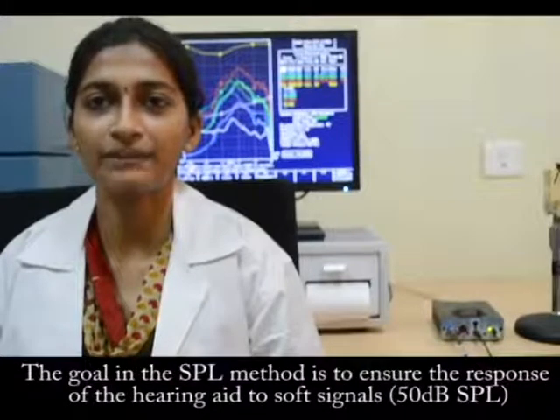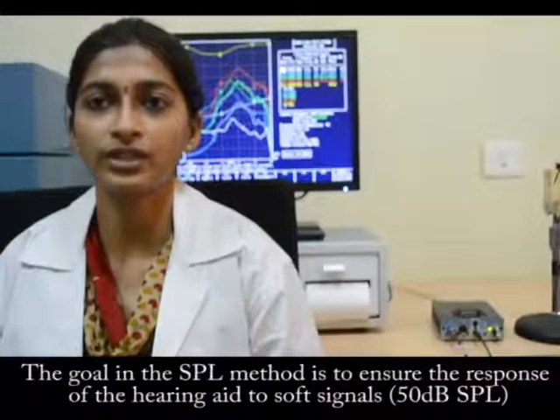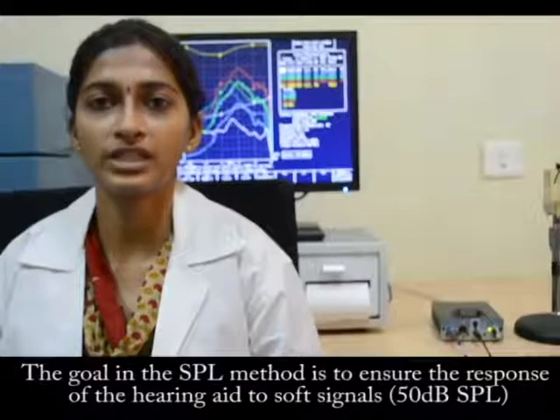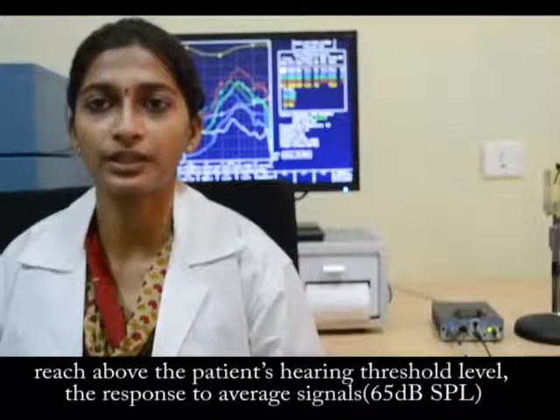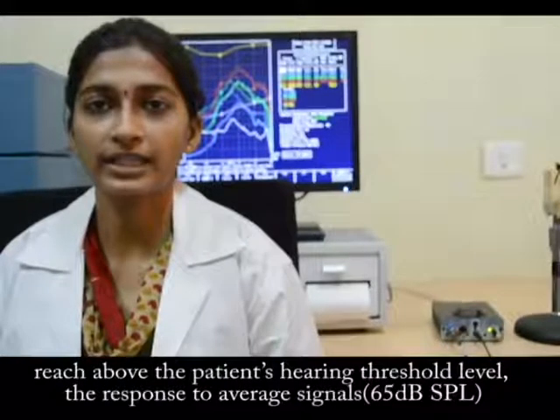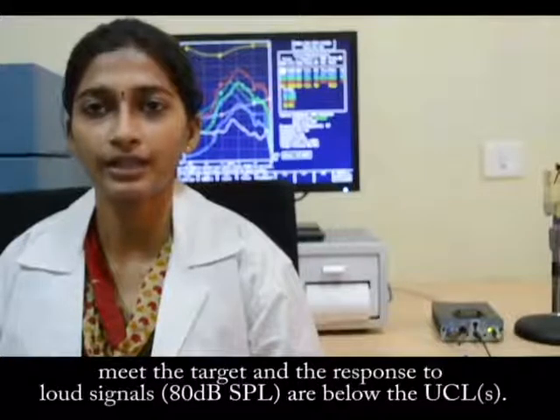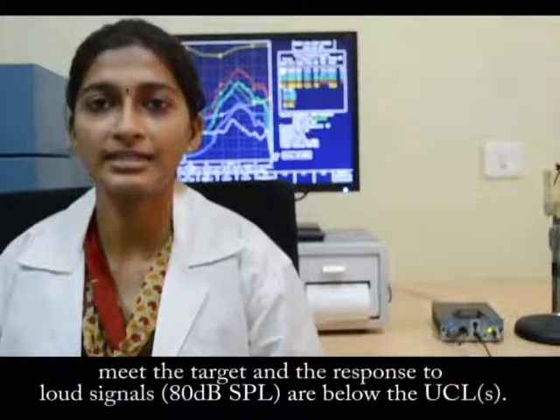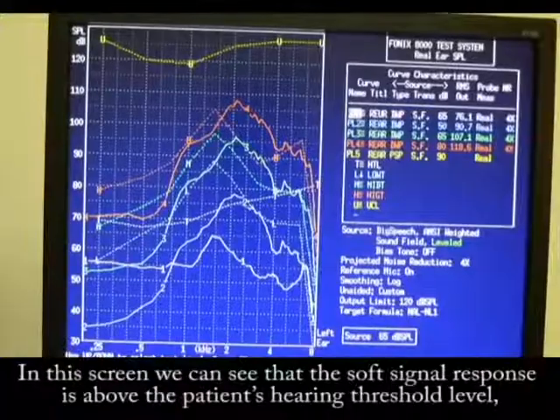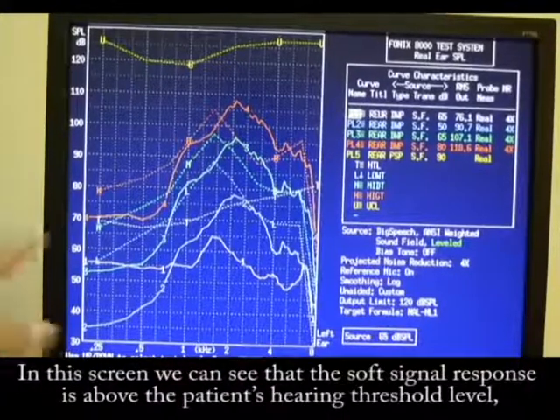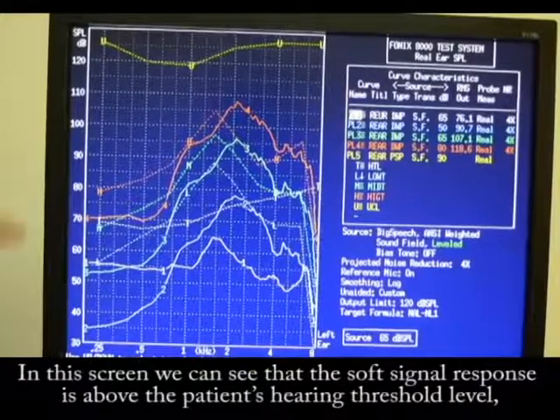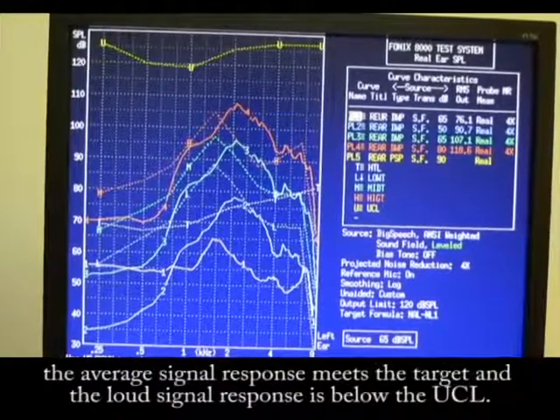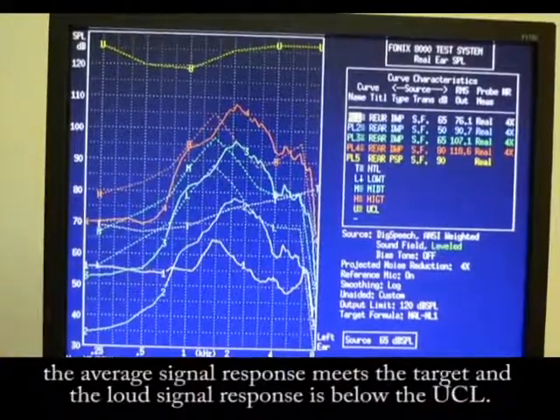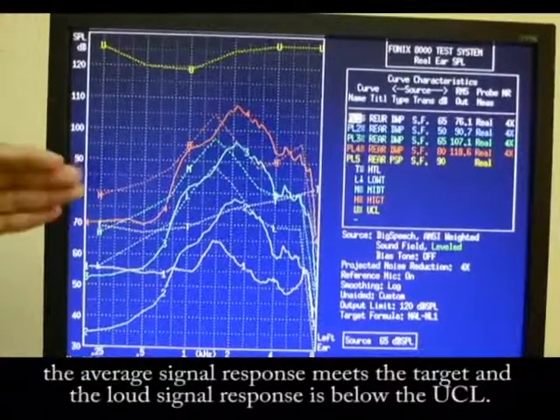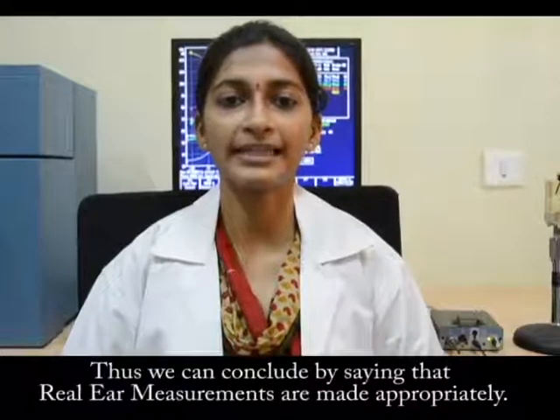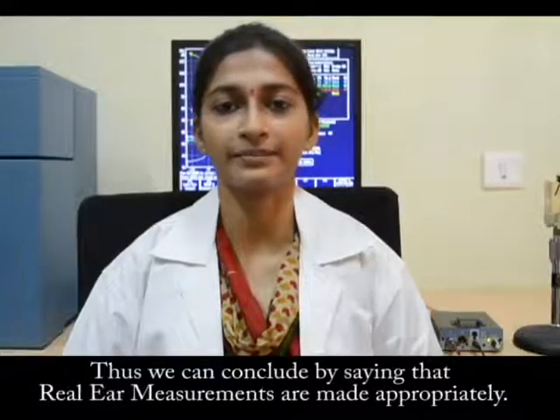The goal in the SPL method is to ensure the response of the hearing aid to soft signals, which is 50 dB SPL, reaches above the patient's hearing threshold levels. The response to average signals, 65 dB SPL, meets the target, and the response to loud signals, 80 dB SPL, is below the UCL. In this screen, we can see that the soft signal response is above the patient's hearing threshold level, the average signal response meets the target, and the loud signal response is below the UCL. Thus, we can conclude by saying that real ear measurements are made appropriately. Thank you.